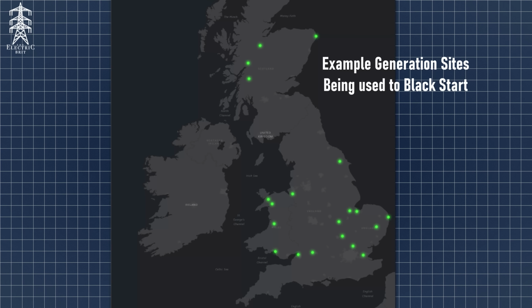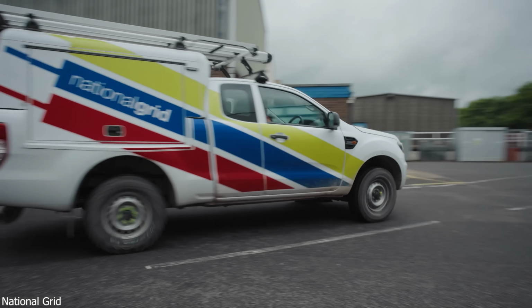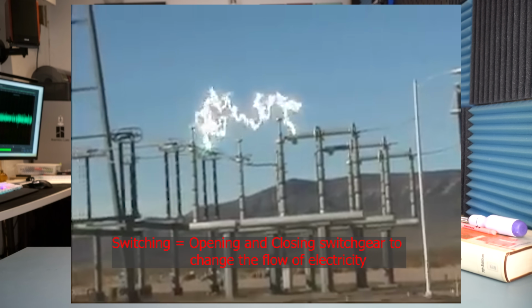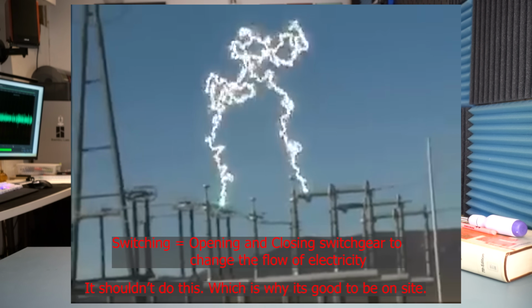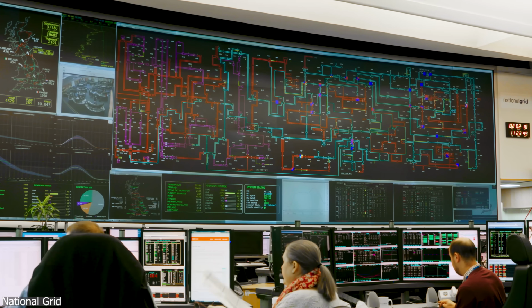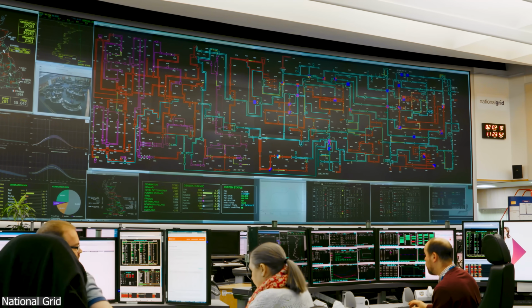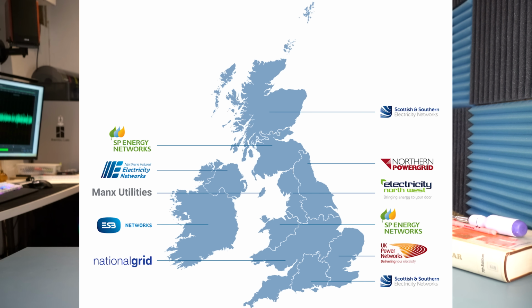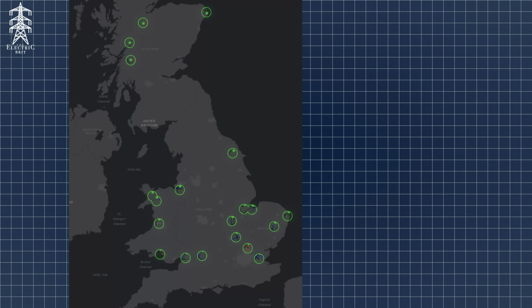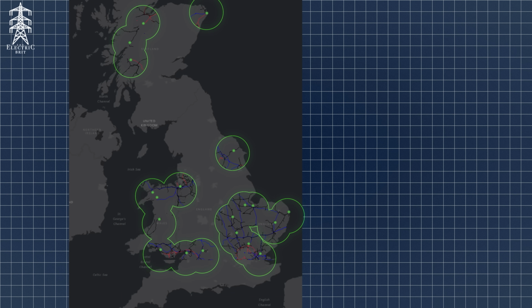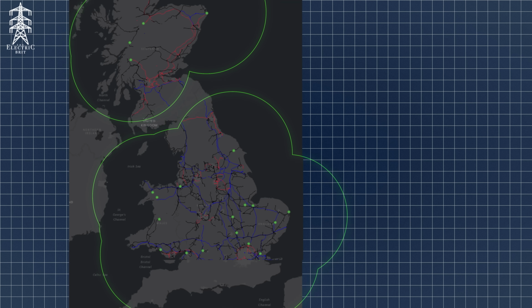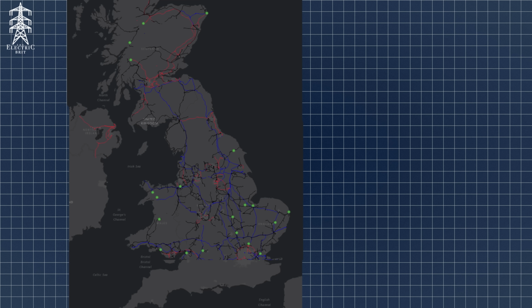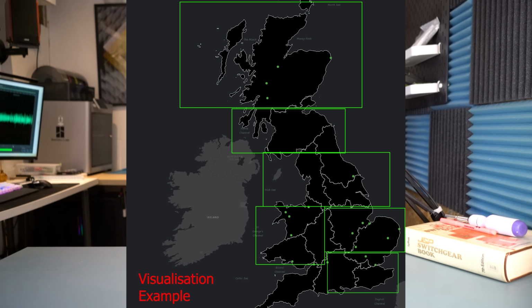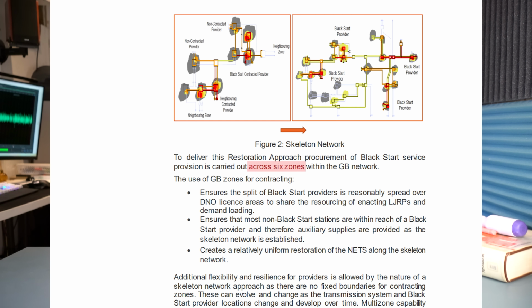So how does the black start happen? Well, these selected sites will be instructed to start generating power, and National Grid engineers will be sent to the substations they connect to for any manual switching to reconfigure the network and to monitor the situation, while the Transmission Network Control Centre, or TNCC, and NESO monitor and instruct remotely, while coordinating with the Distribution Network Operators, or DNOs, to gradually connect load and to ensure the system remains stable as little islands of electricity form. The UK is divided up into black start zones, defined in the NESO strategy, with each zone having its own black start providers, engineers and control strategies to restart independently if needed.